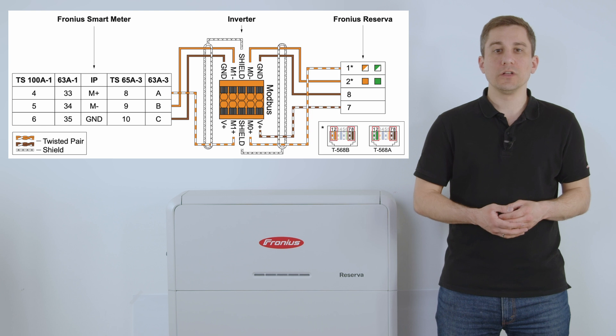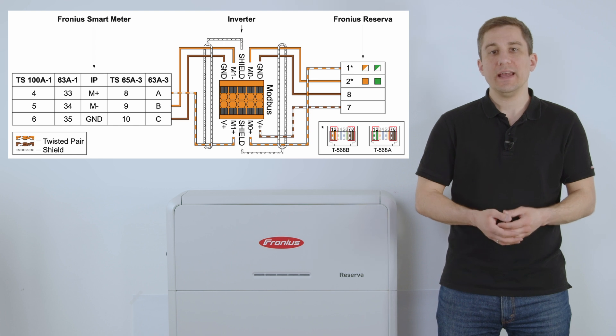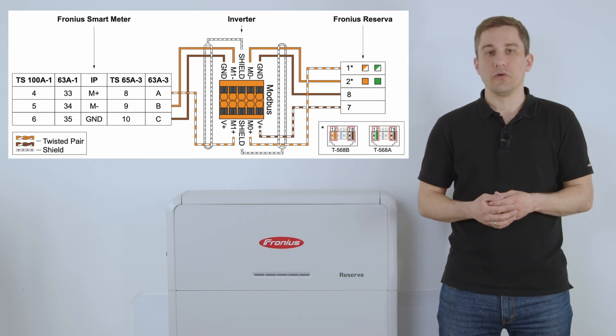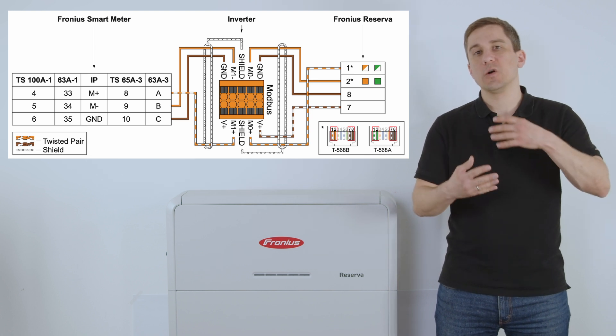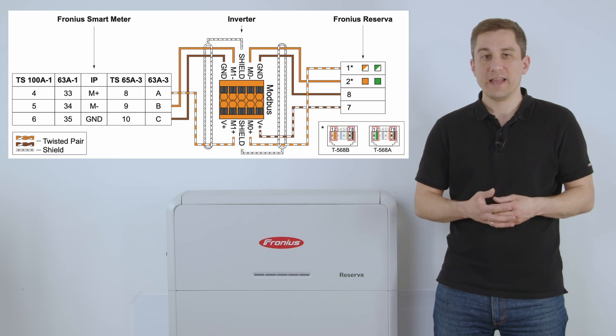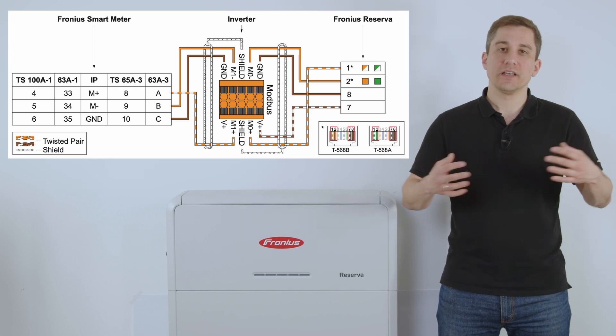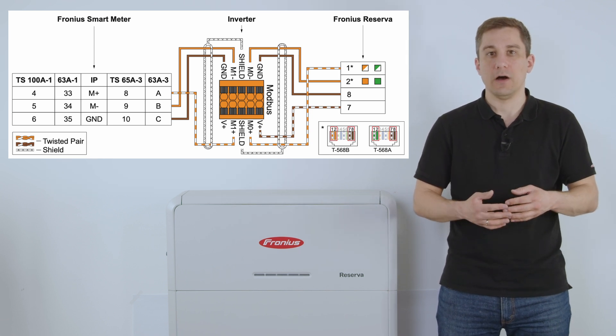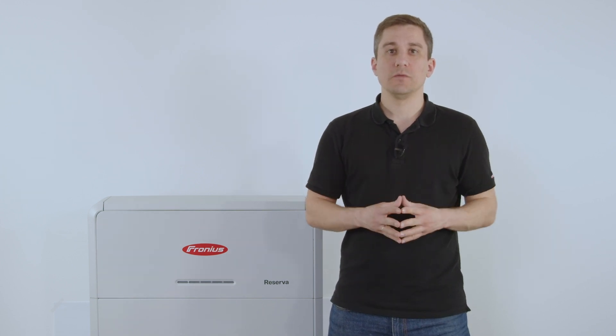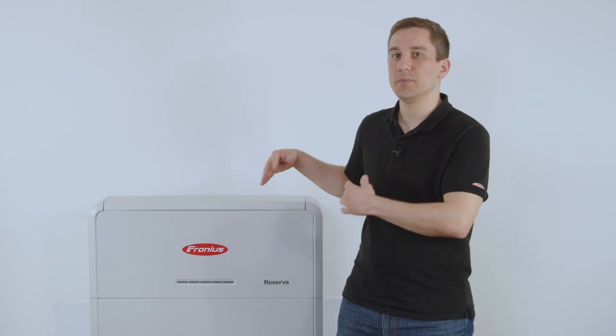For the Smart Meter connection, use M1 Plus, M1 Minus, and ground contact, connecting one side to the Fronius Inverter and the other to the Fronius Smart Meter. Depending on which Smart Meter you use — 100A single phase, 63A single phase, or Smart Meter IP — the contacts differ; refer to the schematic online. For Modbus communication, also ensure the termination resistance is set correctly depending on the system setup.